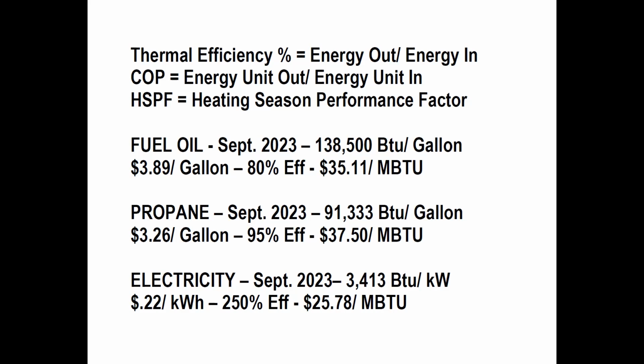Average efficiency, this is where people go down to their basement and they see the oil guys put a tag on there and it says 84% efficient. That's chemical efficiency, it's not thermal efficiency. They measure the CO2 and other products of combustion that come out of the flue and they say, oh, we've converted 84% of it in chemistry. Thermal efficiency is closer to 80% for a good new boiler.